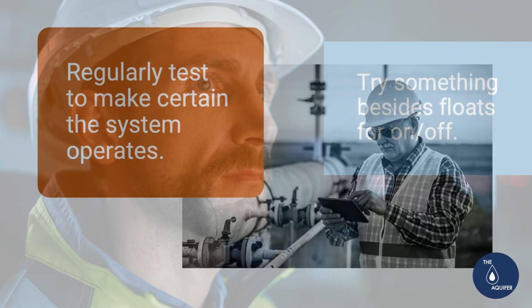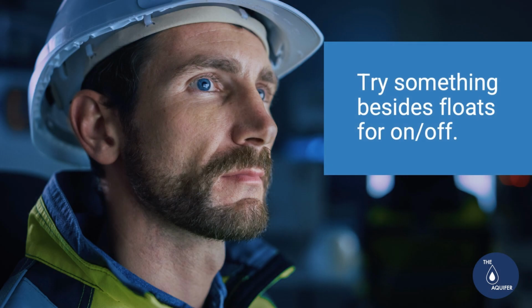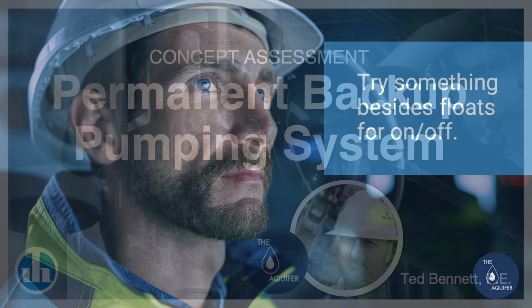And my last recommendation would be to use some technology besides floats for the backup pumping system's on or off control. This would be my number two step towards improving the reliability. But ideally, this would be some kind of analog type signal so you could avoid the need for a control panel, which is a key benefit of the backup pumping system.